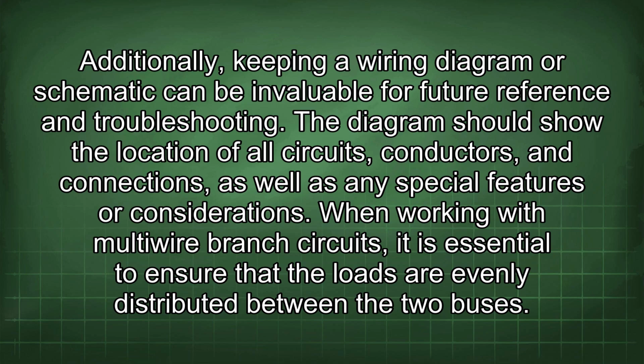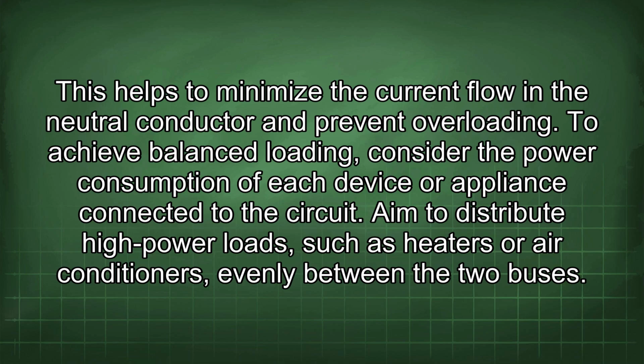When working with multi-wire branch circuits, it is essential to ensure that the loads are evenly distributed between the 2 buses. This helps to minimize the current flow in the neutral conductor and prevent overloading. To achieve balanced loading, consider the power consumption of each device or appliance connected to the circuit. Aim to distribute high-power loads, such as heaters or air conditioners, evenly between the 2 buses.